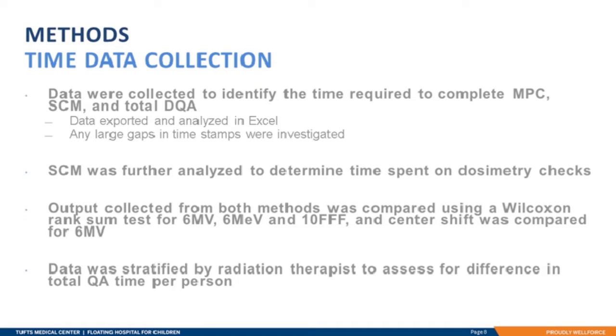Output for a photon, electron, and flattening filter-free beam were collected, as was center shift data for the photon beam. The results from each platform were compared to assess how consistent results were between the two. We also assessed total daily QA time per radiation therapist to assess if there was any variation which may point to a bias due to a training issue.